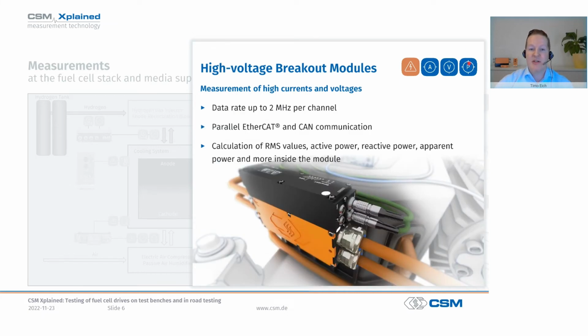The HVBM samples current and voltage at up to 2 megahertz per measuring channel, and these fast signals are then sent on the EtherCAT bus. At the same time, the HVBM also has a CAN bus connection, for example, for the transmission of averaged measurement data in endurance testing. The great thing is now that our HVBM can directly calculate various parameters from current and voltage on board, such as RMS values, active, reactive, apparent power, and the power factor, and then make these available as virtual or calculated channels.